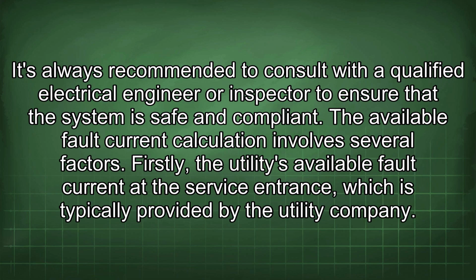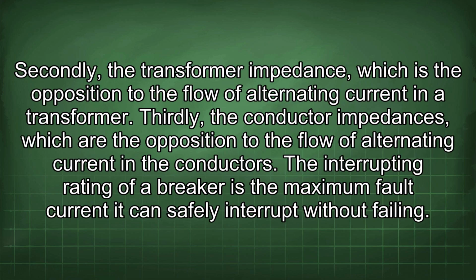The available fault current calculation involves several factors. Firstly, the utility's available fault current at the service entrance, which is typically provided by the utility company. Secondly, the transformer impedance, which is the opposition to the flow of alternating current in a transformer. Thirdly, the conductor impedances, which are the opposition to the flow of alternating current in the conductors.